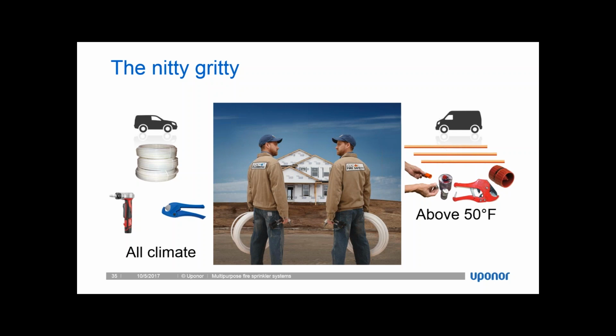On the CPVC side, I need temperatures above 50 degrees Fahrenheit. To use the glue, it's got to be stored above 50 degrees, and it won't work properly if it's not in a 50-degree environment. If it ever freezes, it's not going to work properly after that, even if I'm installing it in an above 50 degree environment. The ratcheting cutter, I can't use below 50 degrees because it creates environmental stress cracking on the CPVC. So at that point, I have to use some sort of chop saw or hacksaw to cut through the pipe, or a wheel cutter would be acceptable too. So if I don't have an environment that's above 50 degrees, now I have to produce heat for that installation.